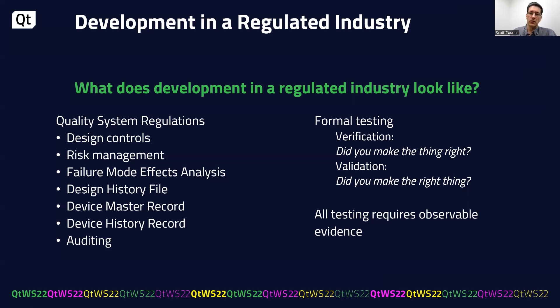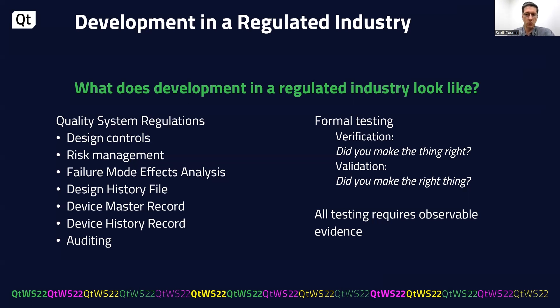The testing regime revolves around verification and validation. This is often phrased as: did you make the right thing versus did you make the thing right? Validation is our indication that the customer will see real clinical benefit. Verification is our assurance that we met our own requirements. All of this testing requires observable evidence — it must be unambiguous and verifiable by a third party. Think: the temperature monitor read 55 degrees Celsius, not the system was hot.